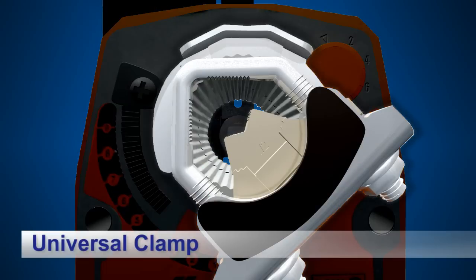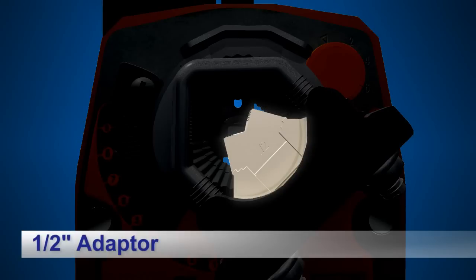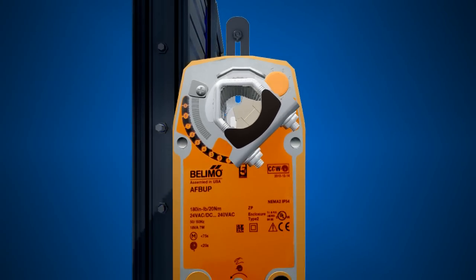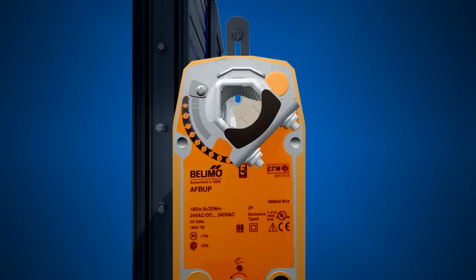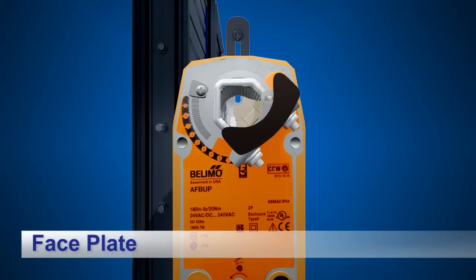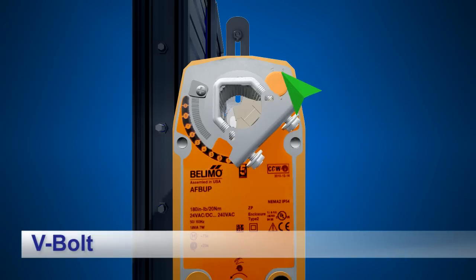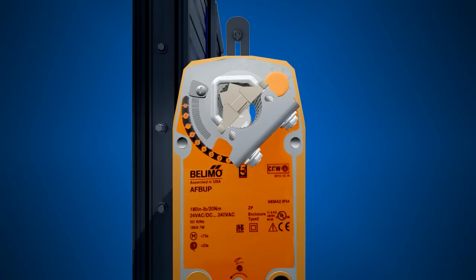Next, adjust the universal clamp so that it will accommodate the 1-inch diameter of the jackshaft. A new Belimo actuator ships from the manufacturer with the 1/2-inch adapter inserted in the tooth block of the universal clamp. This adapter must be removed in order to allow the actuator to fit over the jackshaft. To remove the adapter, slip the retaining clip off the universal clamp. Remove the black plastic faceplate from the universal clamp and slide the V-bolt all the way up to enable you to lift the tooth block and adapter sufficiently to remove the adapter.